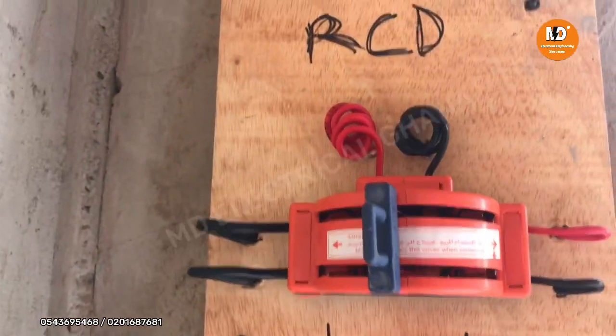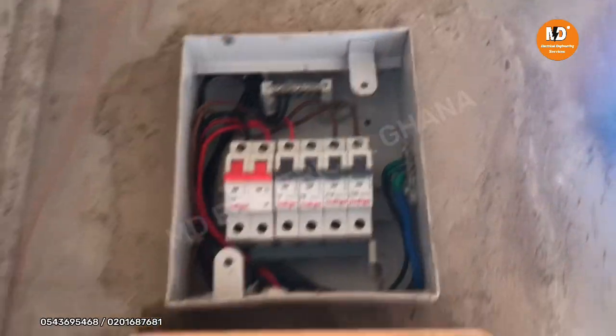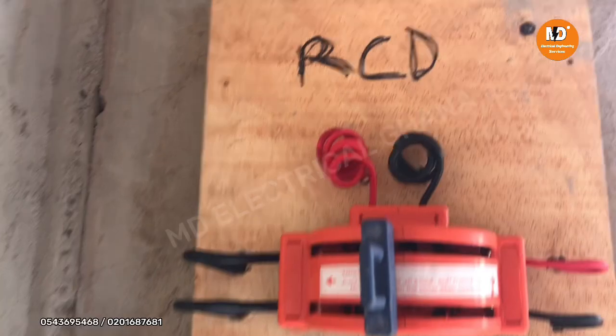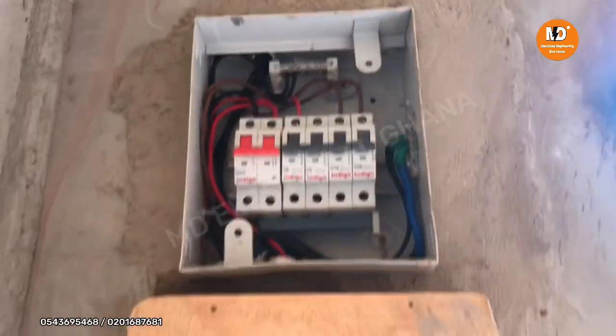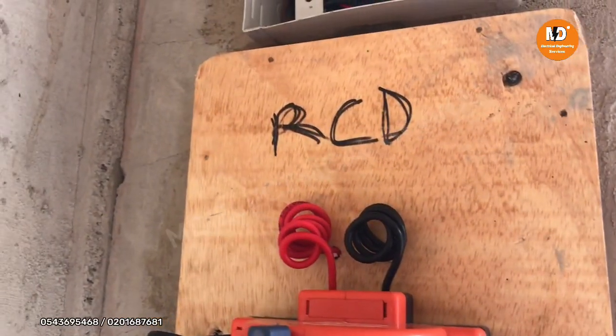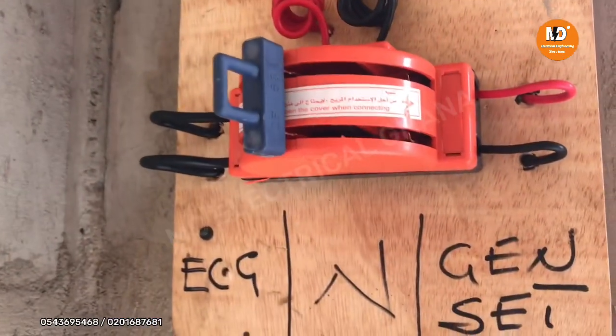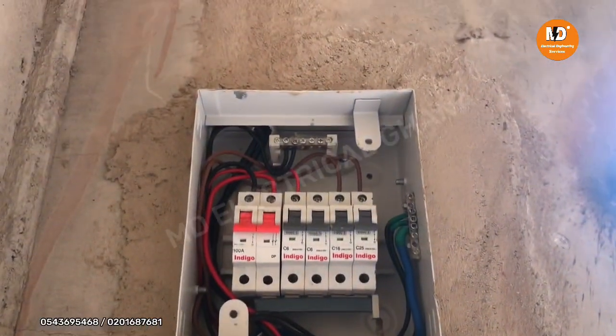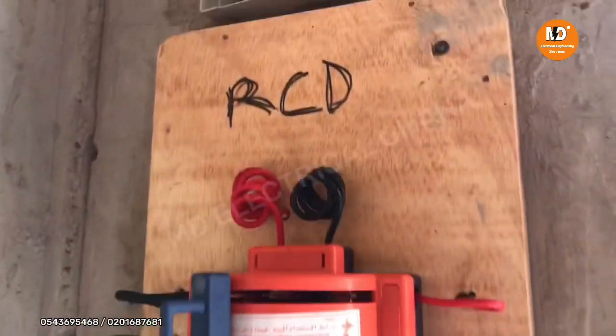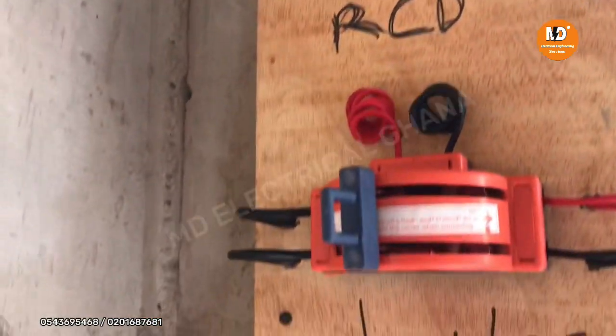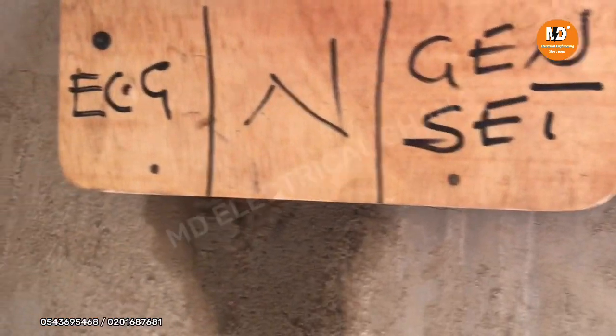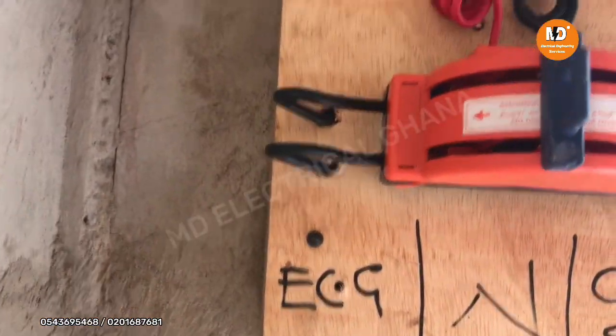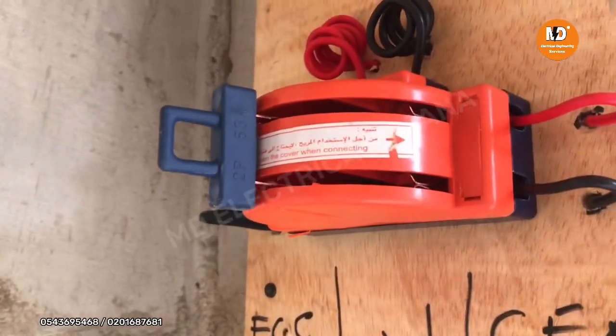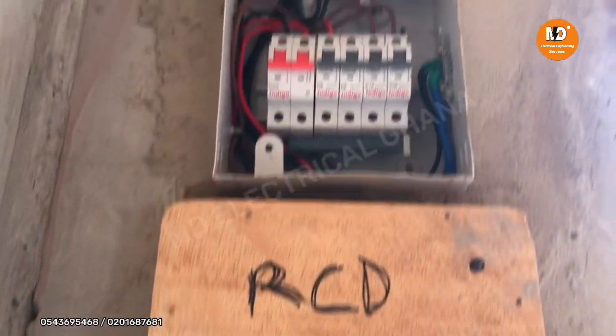So as you can see on your screen, that's our changeover switch neatly installed on the meter board. But for now, we've not installed the RCD, but definitely we're gonna install it. Yes, because an RCD is also a protective device, and it's very sensitive. I love using RCDs because it monitors current leakages, leakage current to the earthing system. It monitors it very well. So we're gonna install an RCD right there.